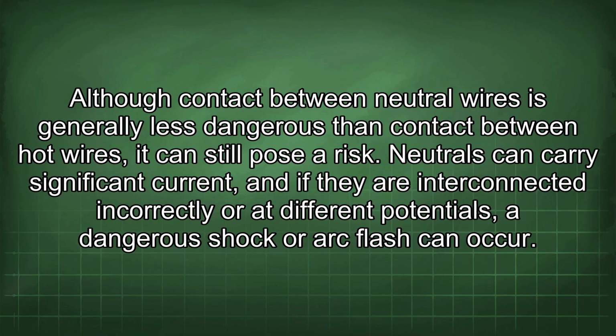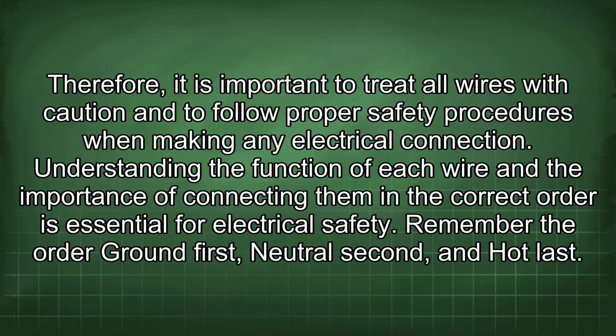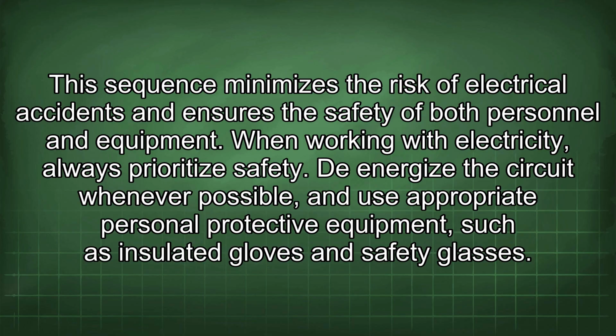Although contact between neutral wires is generally less dangerous than contact between hot wires, it can still pose a risk. Neutrals can carry significant current, and if they are interconnected incorrectly or at different potentials, a dangerous shock or arc flash can occur. Therefore, it is important to treat all wires with caution and to follow proper safety procedures when making any electrical connection. Understanding the function of each wire and the importance of connecting them in the correct order is essential for electrical safety. Remember the order: ground first, neutral second, and hot last. This sequence minimizes the risk of electrical accidents and ensures the safety of both personnel and equipment.